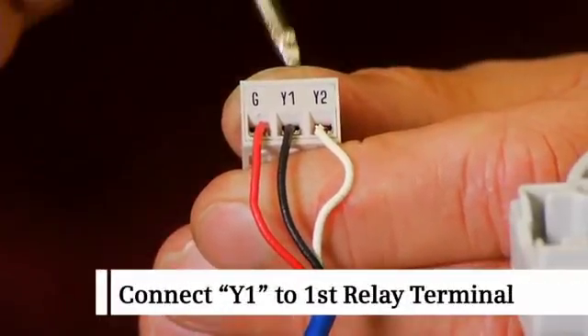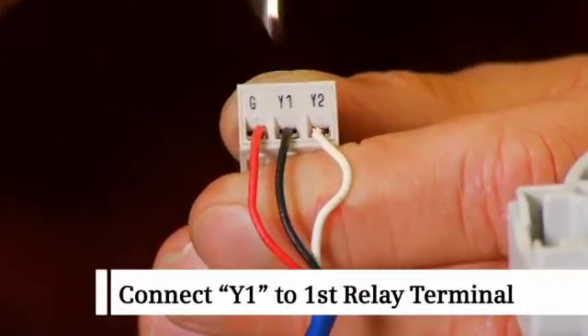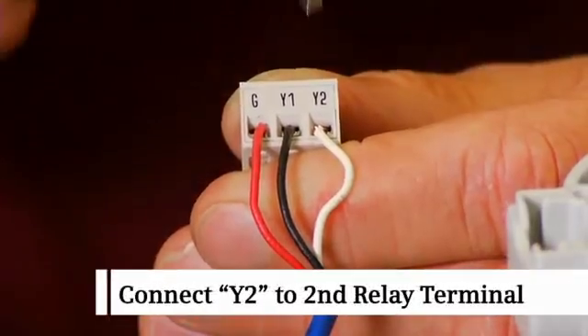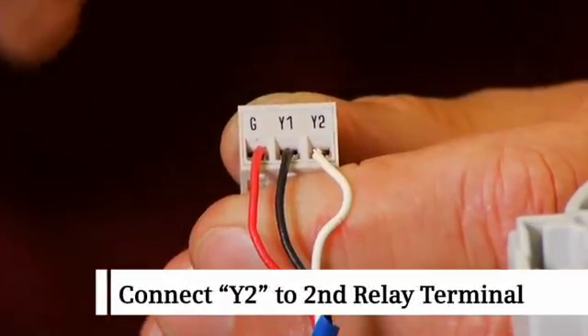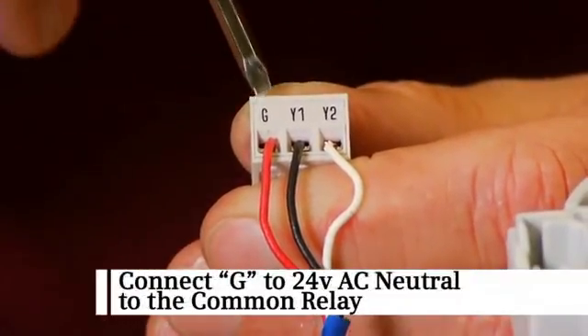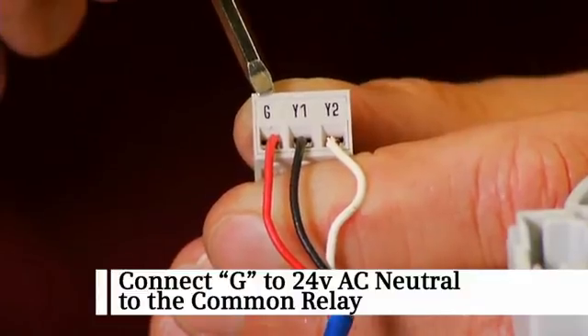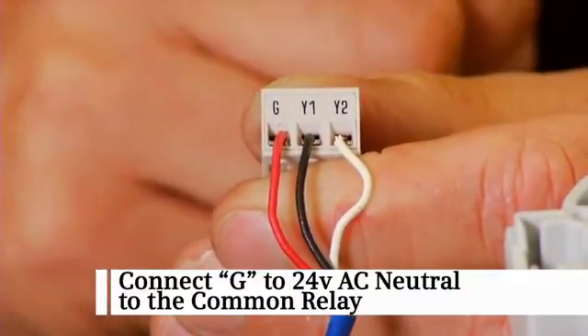Connect Y1 to the first relay terminal. Connect Y2 to the second relay terminal. And connect G to the 24 volt AC neutral to the common relay terminal.